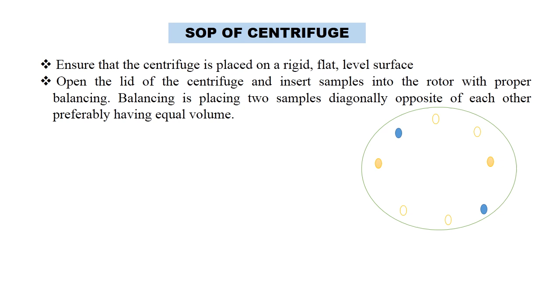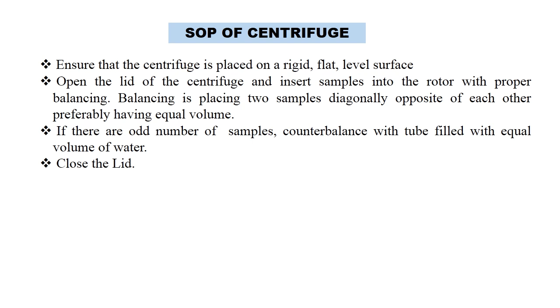In this figure, you can see that the samples in the rotor are placed diagonally opposite, blue to blue, orange to orange. So this is how the setup of samples should be done. This is known as balancing. If there are an odd number of samples, then we should counterbalance with a tube filled with an equal volume of water. Close the lid. Now we have to select the appropriate RPM and time required for the separation and switch on the start button.